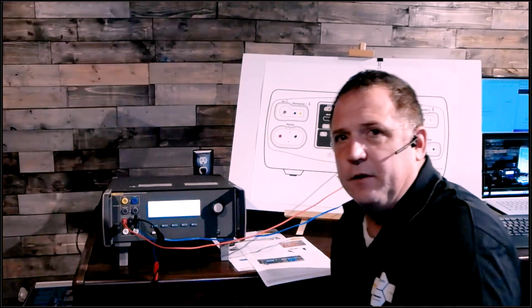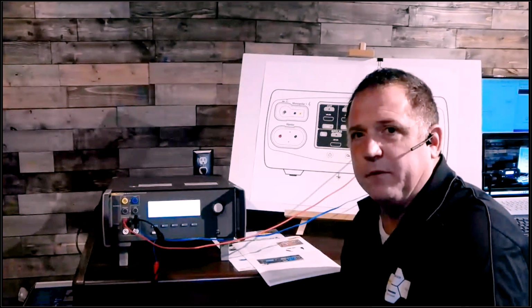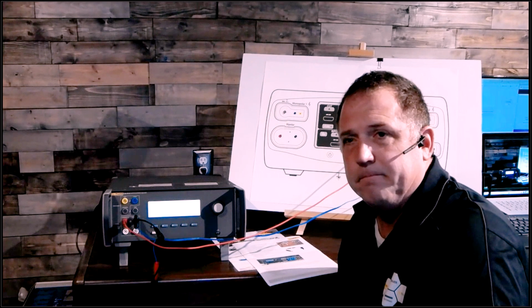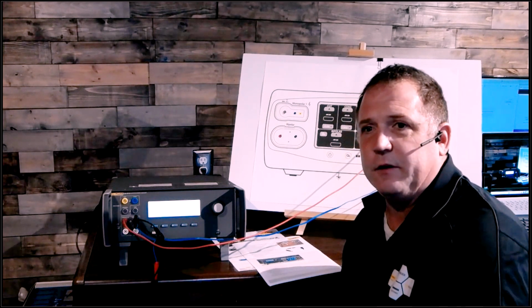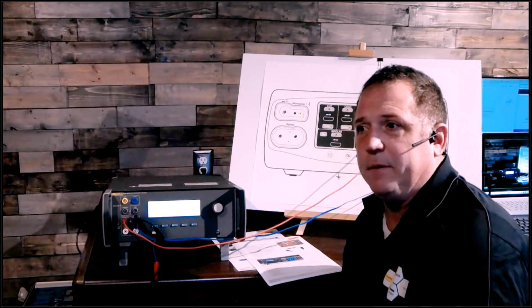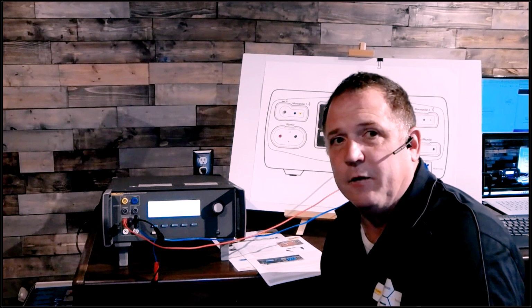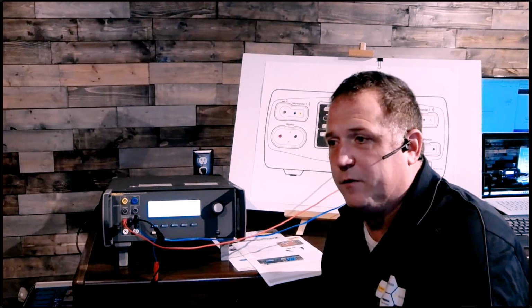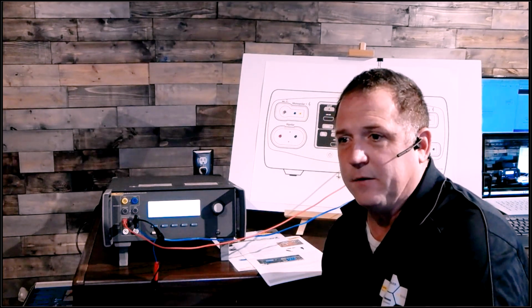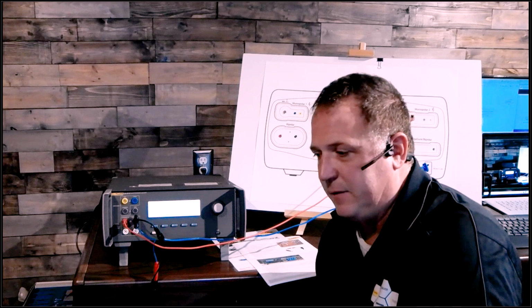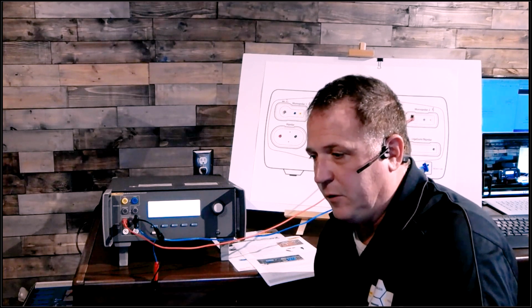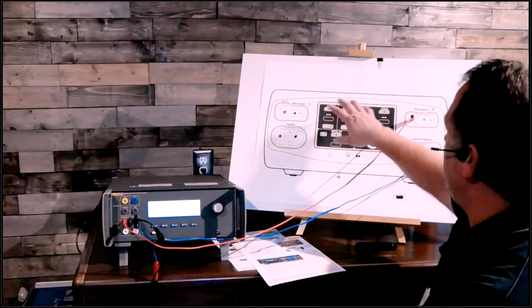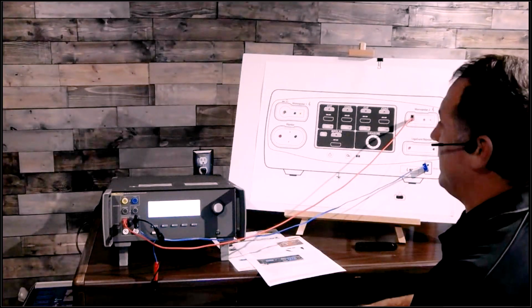How often do you actually get the foot pedal back with the ESU when they say it's broken? I was never usually that fortunate. A lot of times the foot pedal would get lost or broken, and they're running one foot pedal between the ORs - we never had enough foot pedals. So when I had a broken ESU, I never had a foot pedal to test with. So how can I trigger this ESU now with no foot pedal?